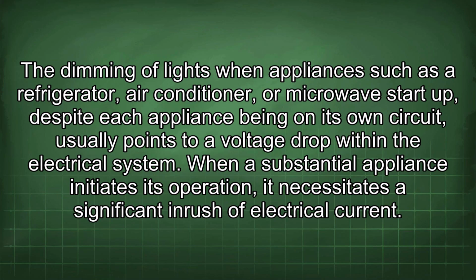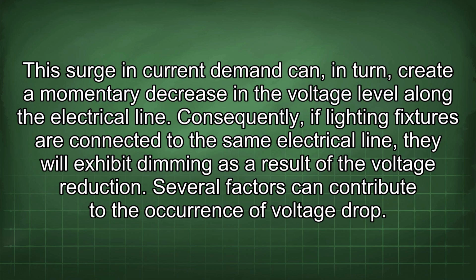The dimming of lights when appliances such as a refrigerator, air conditioner, or microwave start up, despite each appliance being on its own circuit, usually points to voltage drop within the electrical system. When a substantial appliance initiates its operation, it necessitates a significant inrush of electrical current. This surge in current demand can, in turn, create a momentary decrease in the voltage level along the electrical line. Consequently, if lighting fixtures are connected to the same electrical line, they will exhibit dimming as a result of the voltage reduction. Several factors can contribute to the occurrence of voltage drop.